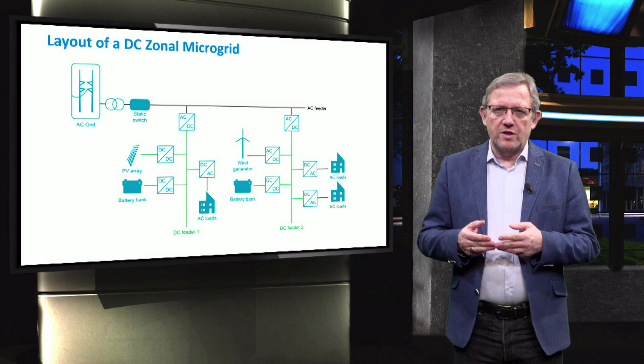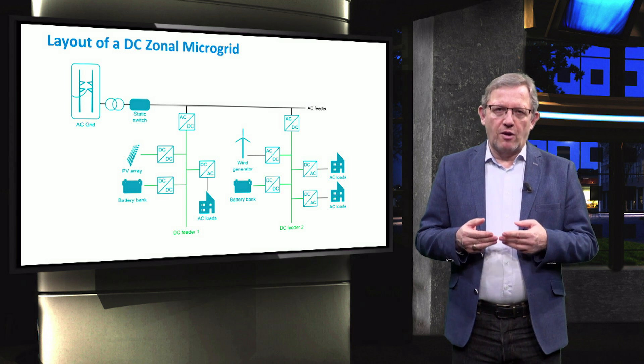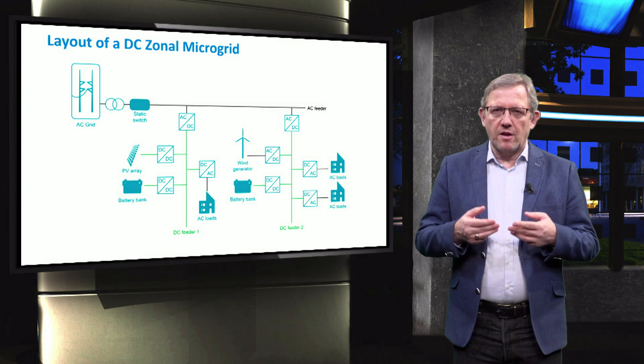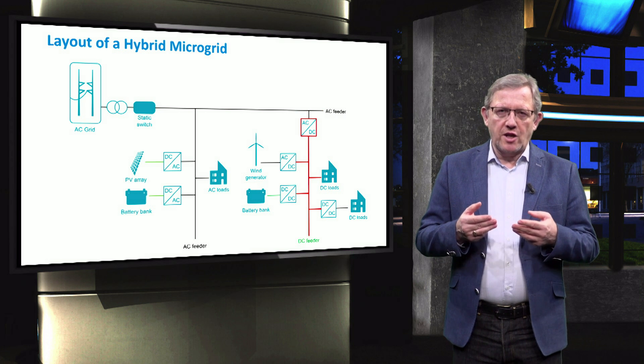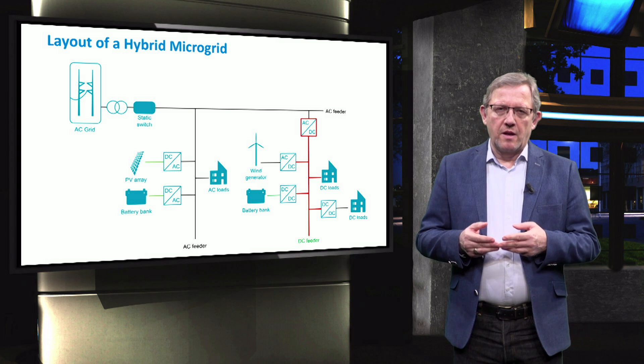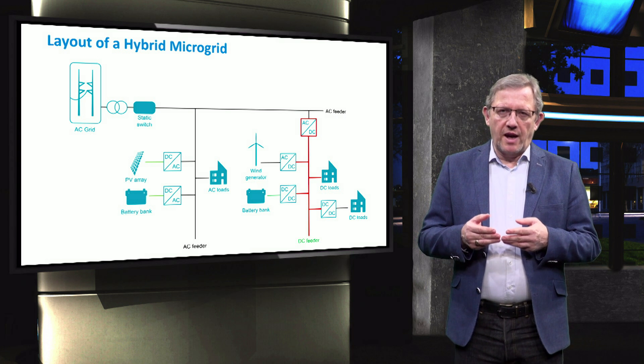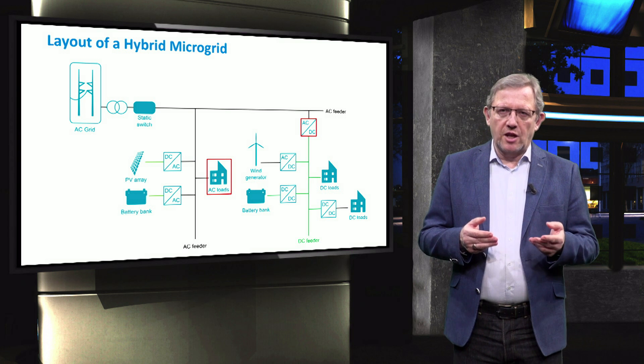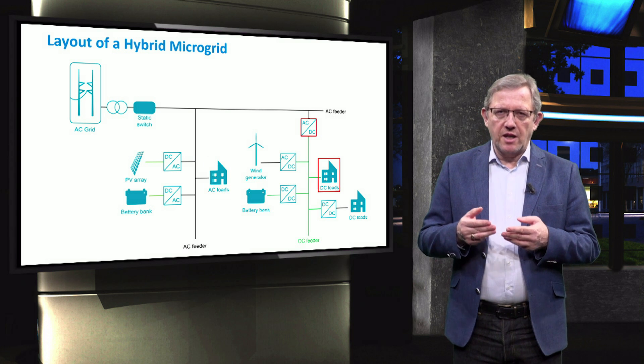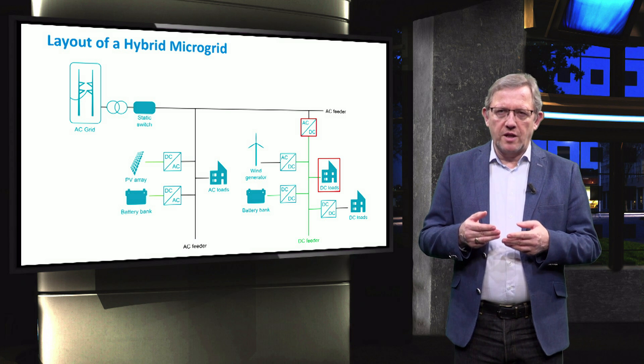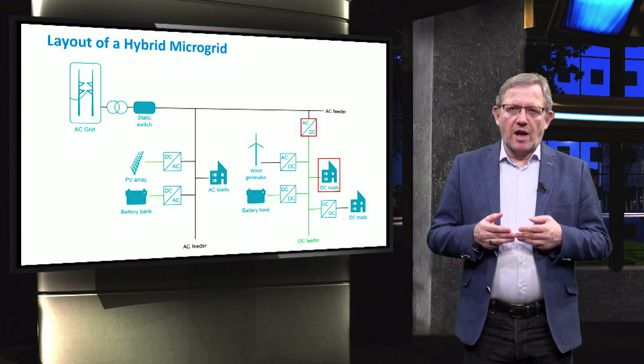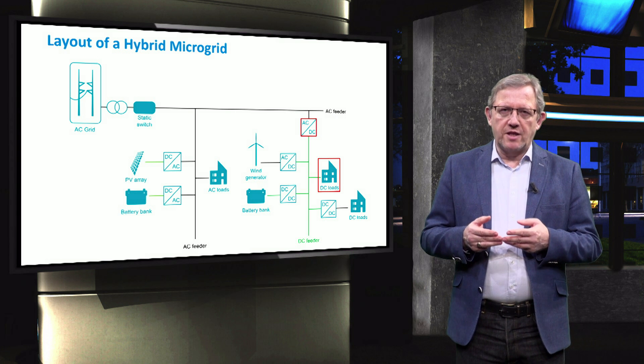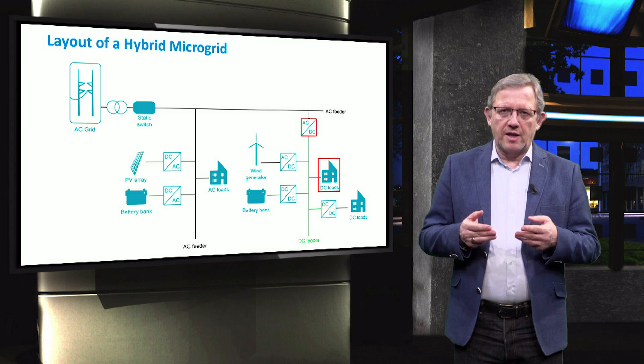The main drawback of the DC zonal architecture is increased complexity due to the interconnection between feeders. The AC-to-DC hybrid microgrid architecture consists of an AC microgrid with a DC subgrid tied together by a bidirectional AC-to-DC converter. Distributed generators can be connected to either the AC or the DC feeders. AC loads are connected to the AC feeder, whereas DC loads are connected to the DC feeder using a power converter to adapt the voltage level if necessary. The DC subgrid can act as a generator or a load of the AC microgrid depending on the power balance at the DC feeder.